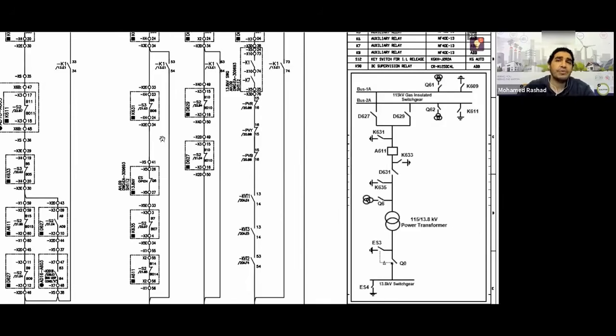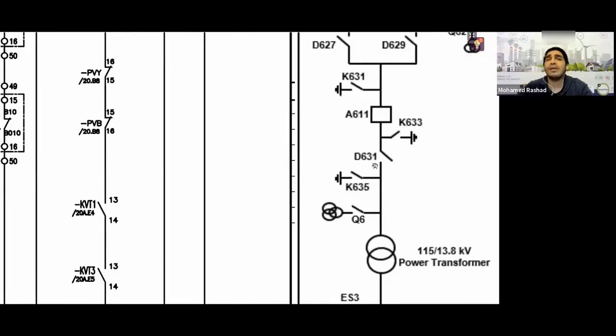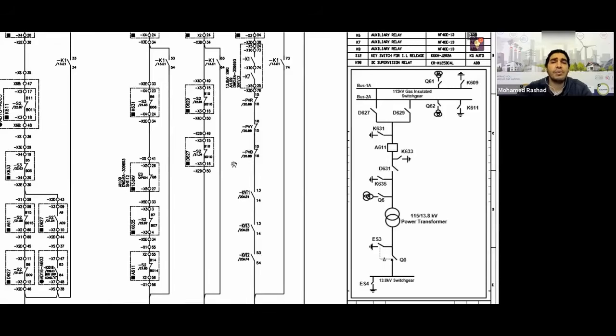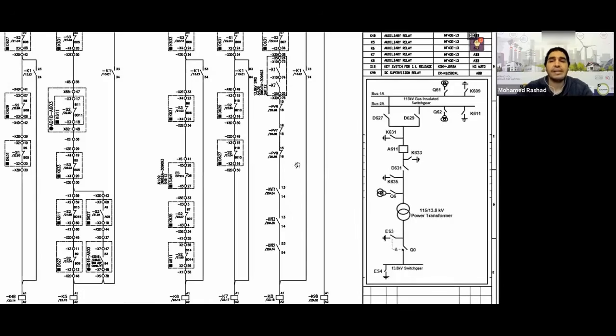Now let's look at the two important things that differ. In the case of the transformer, as for the overhead line, there won't be any difference. They are very straightforward, very easy. Who are they? They are the disconnector switch, which is the line disconnector, and the line earth switch. These are extremely important, so let's take it step by step. Regarding the line disconnector, we agreed that the disconnector looks at the breaker and the grounds.